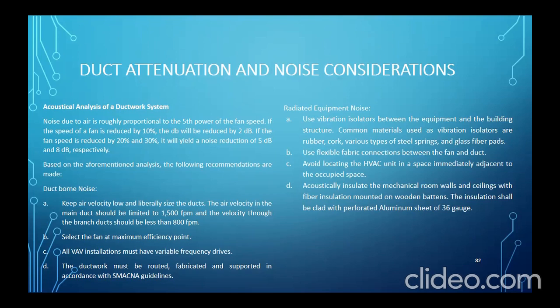D. Acoustically insulate the mechanical room walls and ceiling with fiber insulation mounted on wooden battens. The insulation shall be clad with perforated aluminum sheet of 36 gauge. Manipis na yan. So, kung katabi yung room mo, kailangan mo ng insulation. Acoustic insulation.